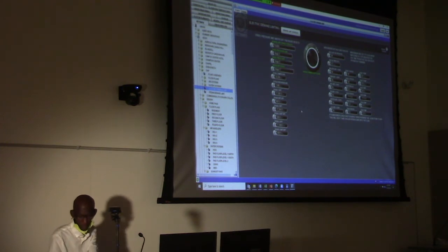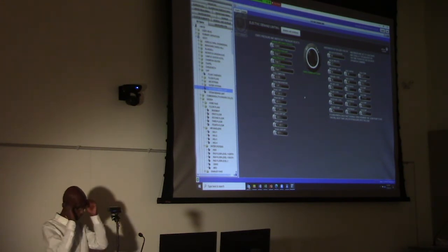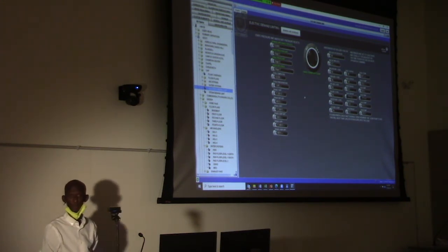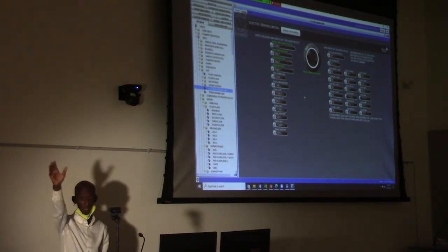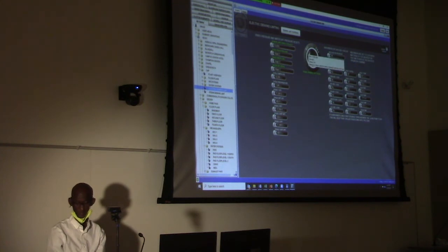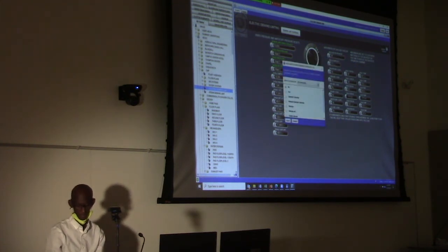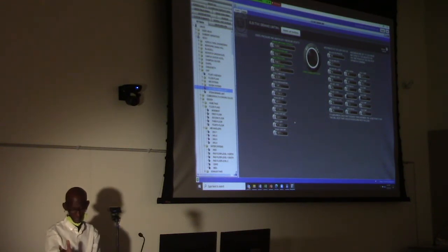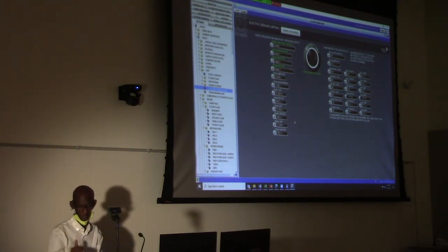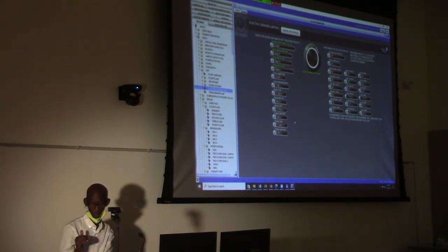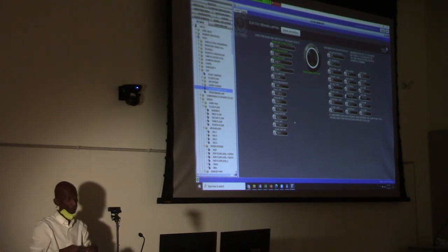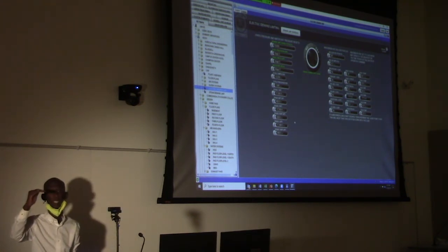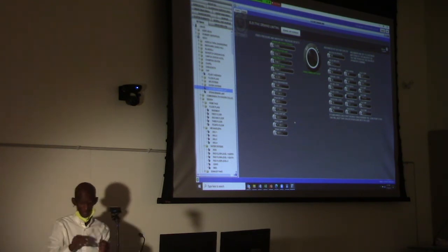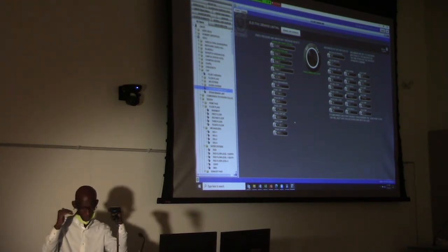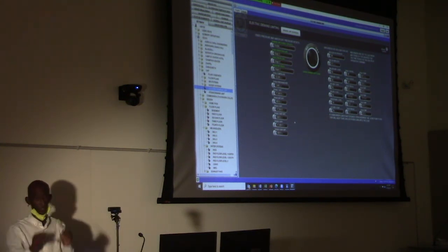So what we do here, we have multiple stages. When we get a call to curtail our electrical demand, folks at the power plant go through this button here, they click on yes, and all of a sudden we use stage 1 and 2. Stage 1 looks at every non-lab building, and it slows down their air handling unit. And it looks at those buildings too, it reduces the static pressure.